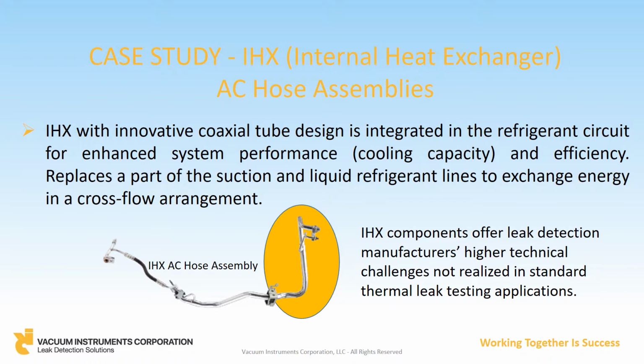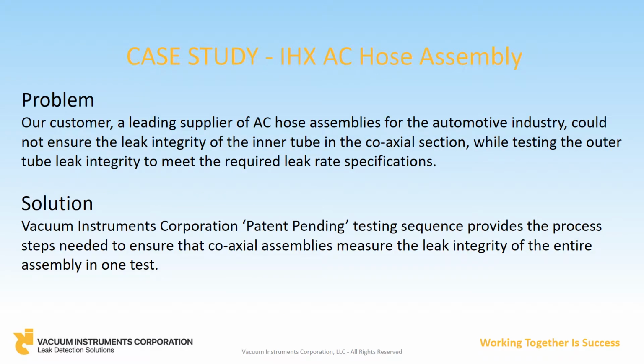IHX components present leak detection manufacturers with higher technical challenges not seen in standard thermal leak testing applications because of their coaxial section design. The presented case study will demonstrate this point. Our customer, a leading supplier of automotive AC hose assemblies, was performing the accumulation method of leak detection. But this method could not ensure the leak integrity of the inner tube in the coaxial hose assembly and test to the leak rate specification. So the customer turned to VIC to solve the application problem.